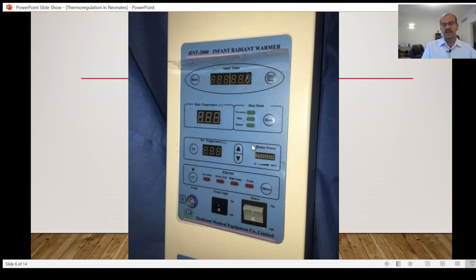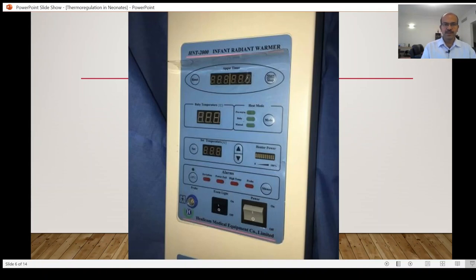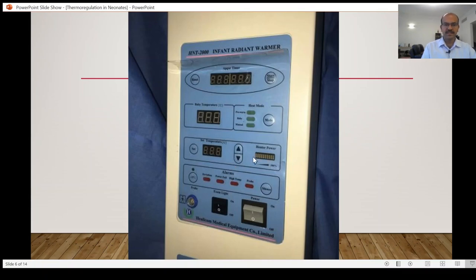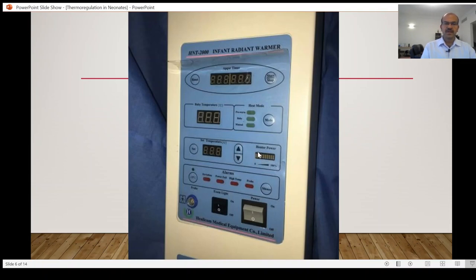Usually when you go to the labor room, we have kept the warmer there on a pre-warm mode so that the towel and everything kept under it is kept heated. However, when you are actually attending the delivery, it's better to change it to the manual mode because the pre-warm mode keeps dropping the heater output every few minutes and it reaches 30 percent and stays there.